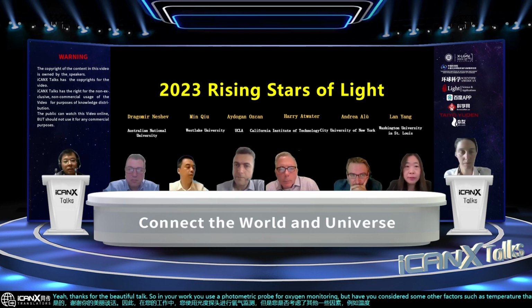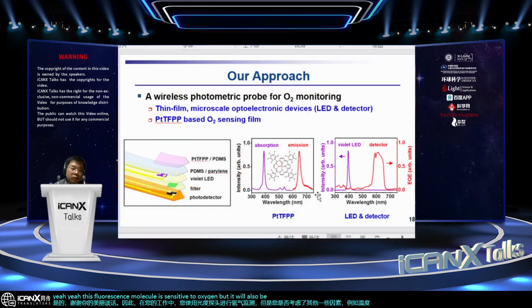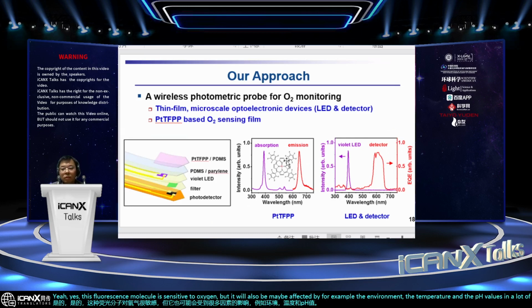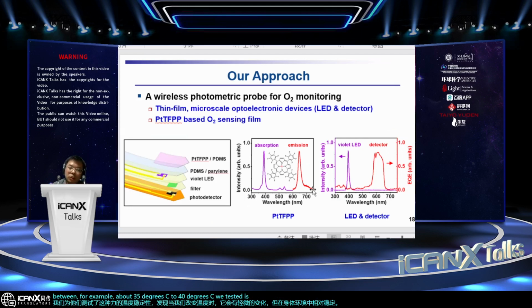Yes, this fluorescence molecule is sensitive to oxygen, but it may also be affected by, for example, the environment temperature, the pH values, and a lot of factors. We tested the temperature stability of this phosphor, and we find that it has a slight change when we change the temperature, but it's relatively stable in the body environment, for example between about 35 degrees C and 40 degrees C. And in our body environment, we know that temperature will not change too much, usually just about 1 to 2 degrees C. Yeah. Okay, thank you.